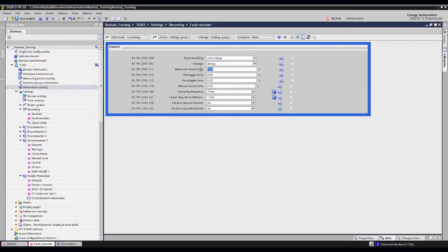Now, when it comes to pre-trigger, how much would you like me to cut from these 5 seconds? Cut them from the 5 seconds, not add to them. From the 5 seconds, how much pre-fault time did you have? So 0.25 is quite sufficient. And after clearance, 0.1 is more than enough for us. Is that clear? Great. Here, it's a simple manual record timing if you're doing manual triggering. How long does it record for?